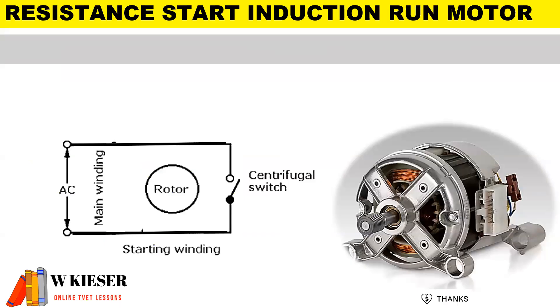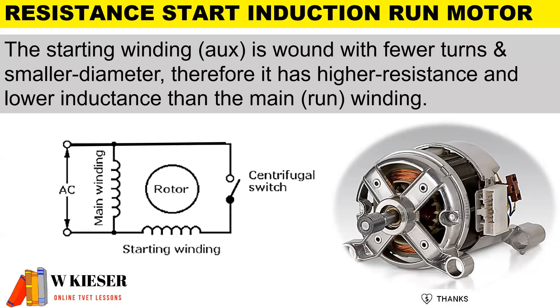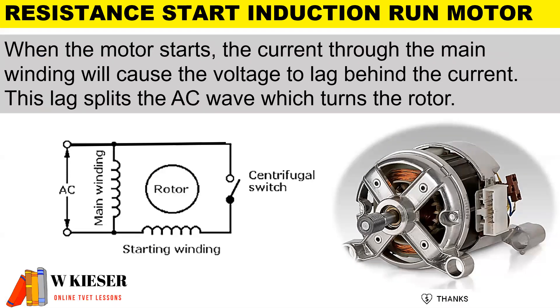In this illustration, we have a resistance start induction run motor. Looking at the circuit diagram, we have the main winding, the start winding, a centrifugal switch, and the rotor. These motors are mainly used for washing machines and have low starting torque. In terms of operation, the start winding has fewer turns and smaller diameter, giving it higher resistance and lower inductance than the main winding. When the motor starts, the current through the main winding causes the voltage to lag behind the current, which splits the AC wave and turns the rotor.